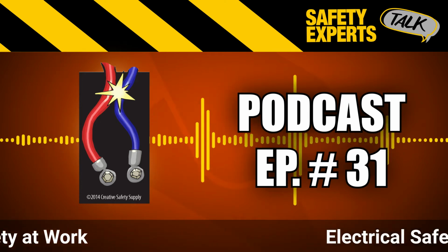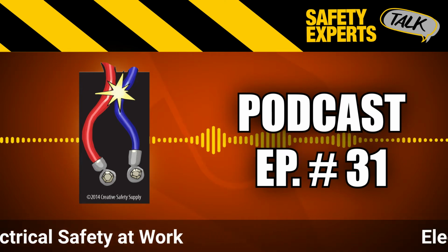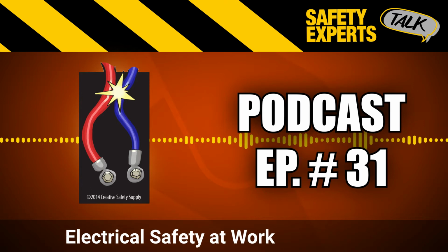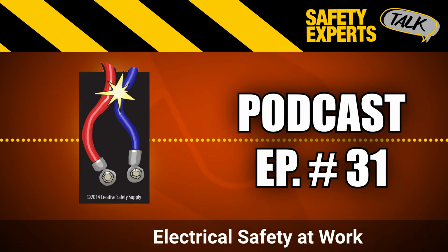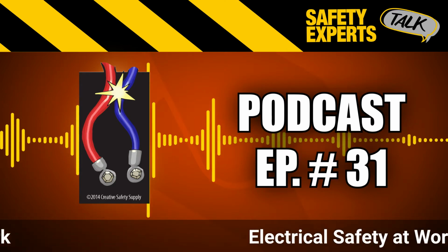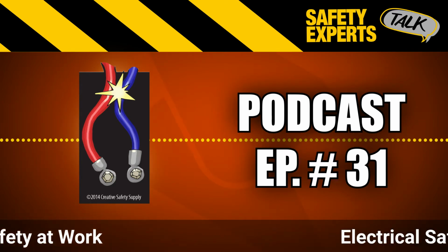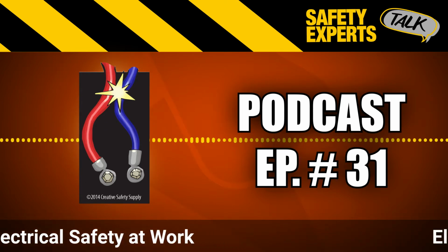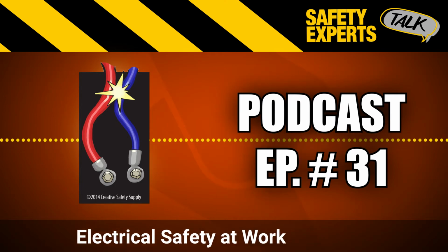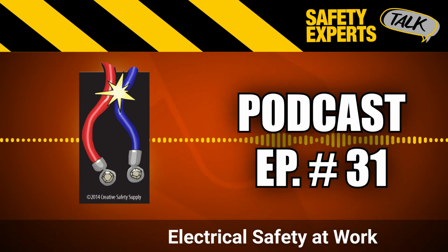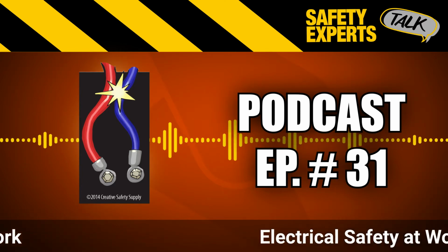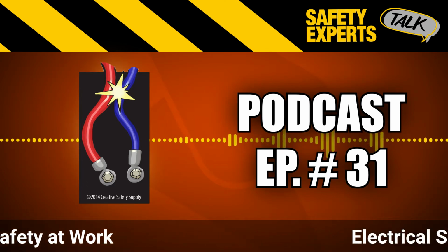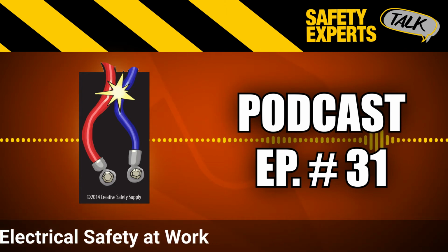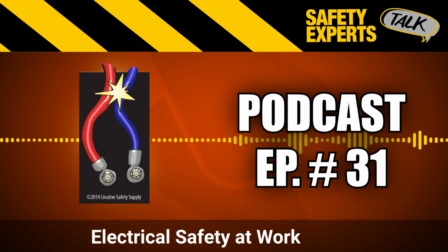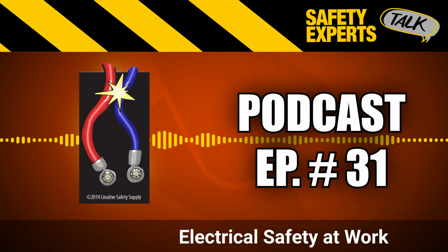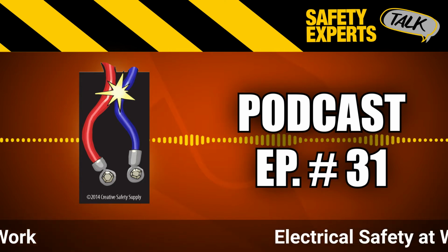One of the things is that the toolbox talk should be effective enough to convey the message that helps the worker understand how to identify electrical hazards and dangers, how to properly inform their supervisor of the hazards, how to protect or identify live parts and contact the supervisor or electrician, and proper electrical lockout tagout techniques so that the electrical side of a piece of equipment is properly de-energized and verified and safe to work on. Proper grounding techniques is the simplest one too, for flexible cords, making sure the cord is in good shape and that the grounding pin is still in contact and working properly.